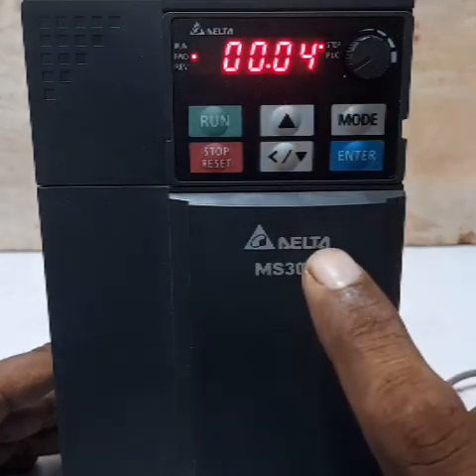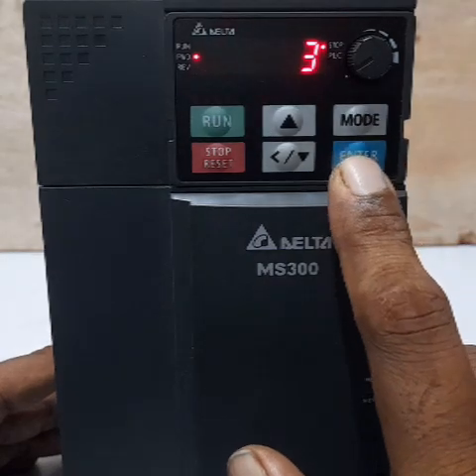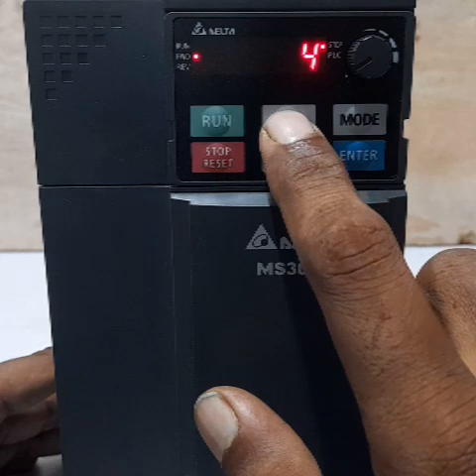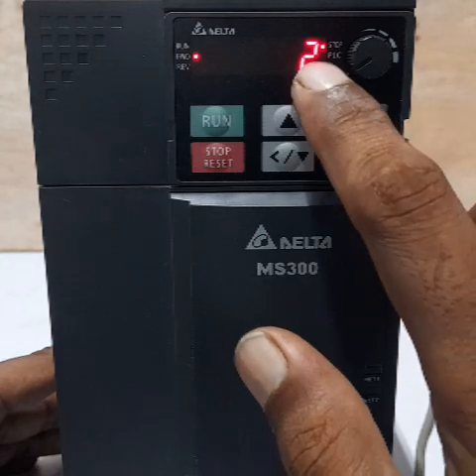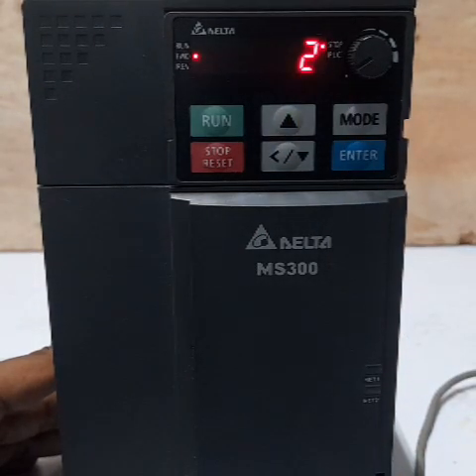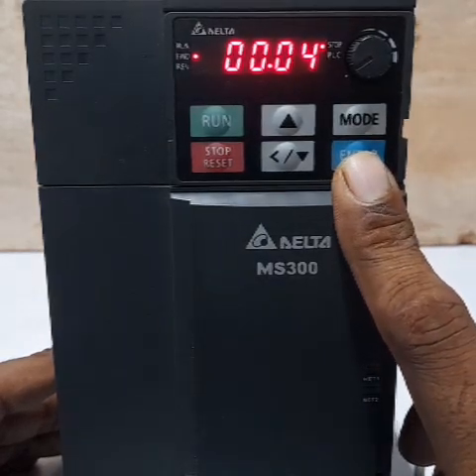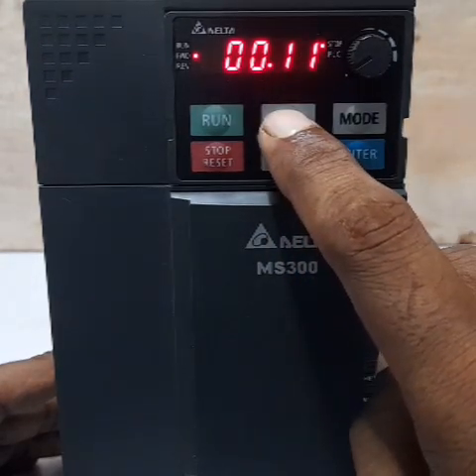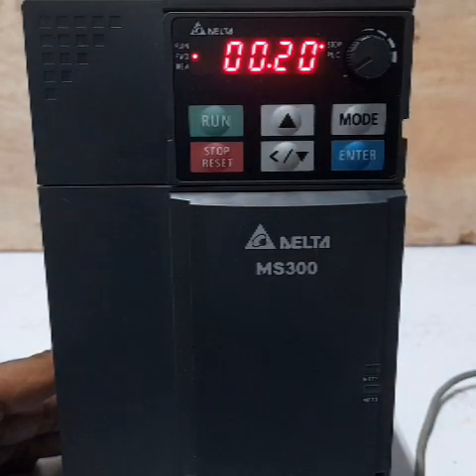Parameter 0.04 is the function display setting. Press Enter — the default is 3, which displays DC bus voltage. Now change it to display the actual output frequency. Enter our needed value, then press Enter. The next setting is master frequency command source, parameter 0.20.